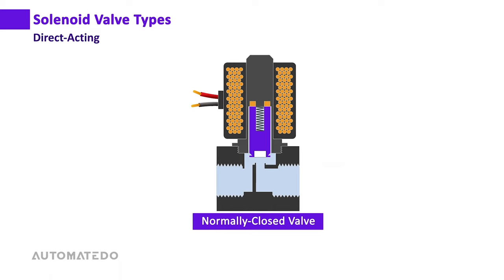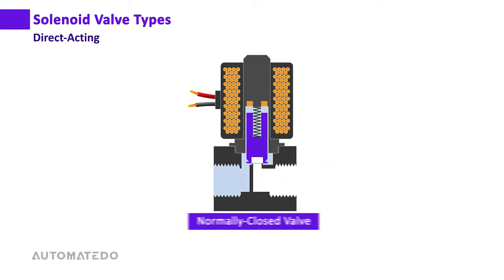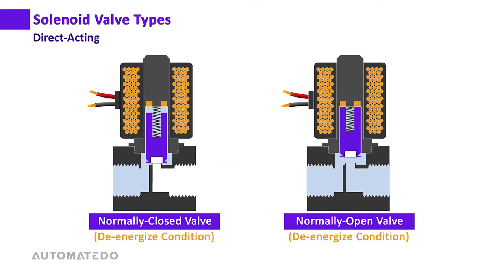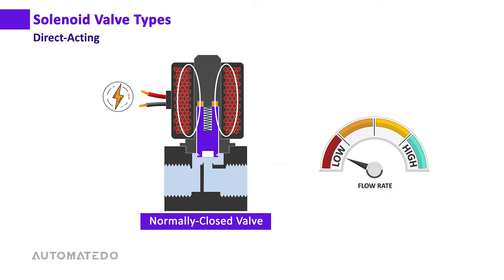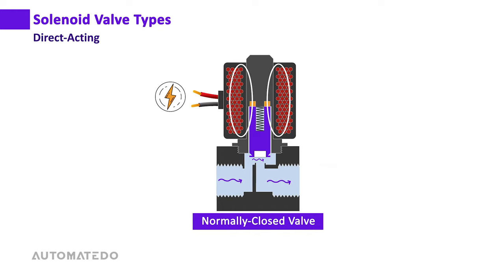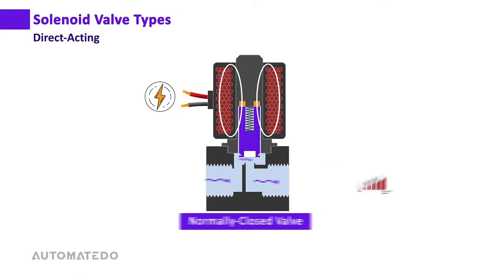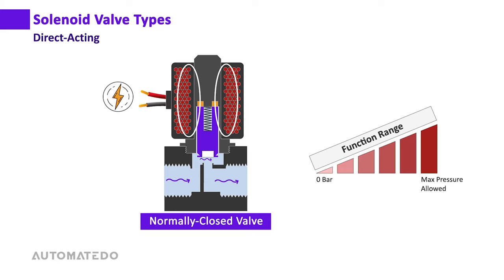Once power is interrupted and electrical current stops flowing, the magnetic field vanishes and the spring pushes the plunger back to close the valve orifice. Note that the normally open valve works the opposite way. The direct acting solenoid valve is used for relatively low flow rates and does not require differential pressure, so it can function from zero bar to the maximum allowed pressure.